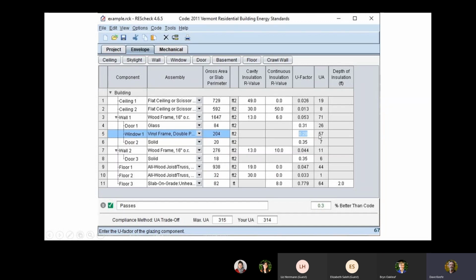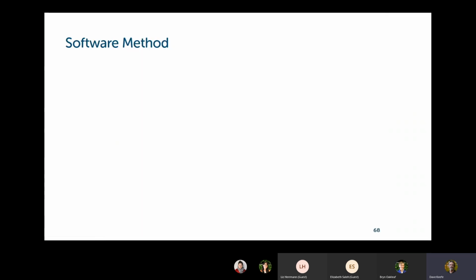But again, the windows are a fair bit of it. So, the windows account for 57 out of the total. So it's just good to go here and look and see, where am I going to make a difference? Am I going to make a difference by treating this ceiling right here? Well, probably not, because it only accounts for 8 to begin with, where I've got all these other components that amount to 50 or 70 or whatever, 40. So the UA can kind of just give you a good feel of where the heat is going. And if you want to stop it, you've got to go to where it's leaving. Okay, on to the next slide.